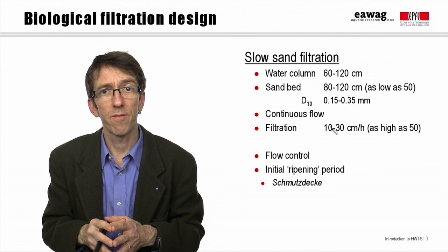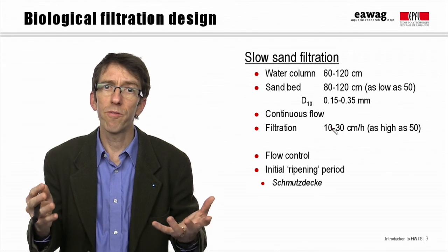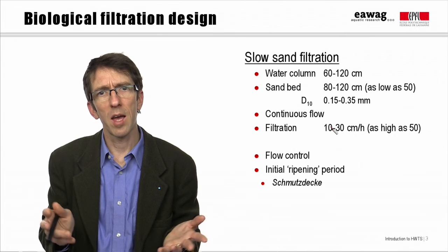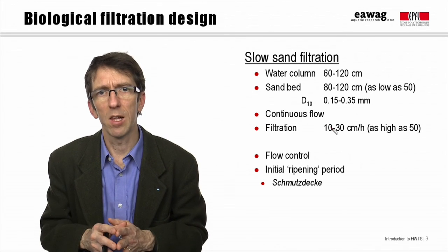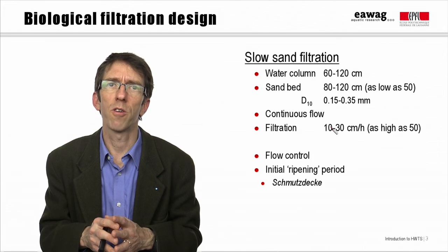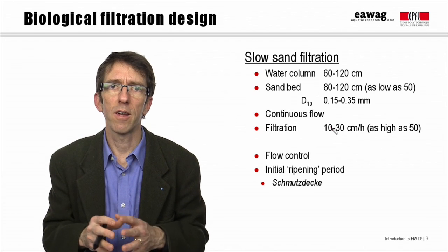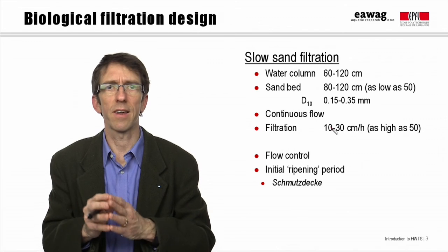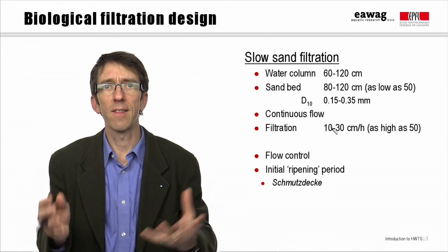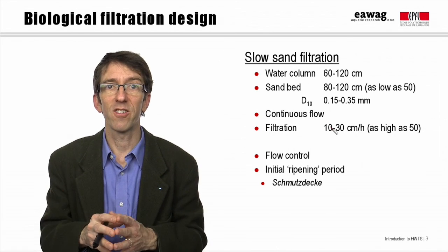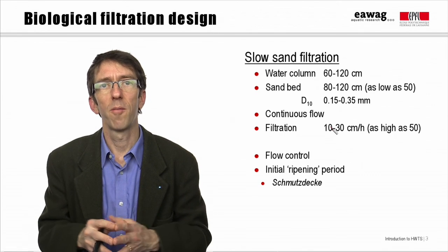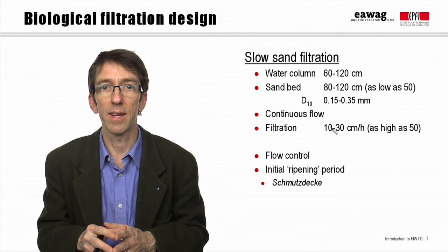Another thing about slow sand filtration is that when putting a new filter online, it takes some time for the biofilm to develop. About a month, usually. It's called a ripening period. And then the layer that forms is called the Schmutzdecke, or the dirty layer, even though that's actually where a lot of the important pathogen removal processes take place.